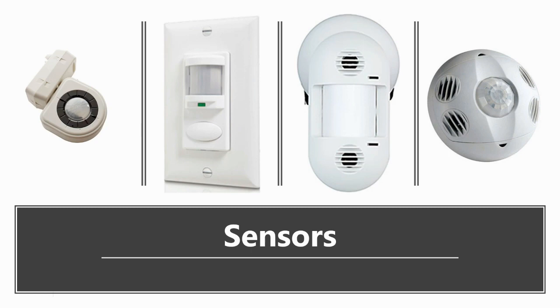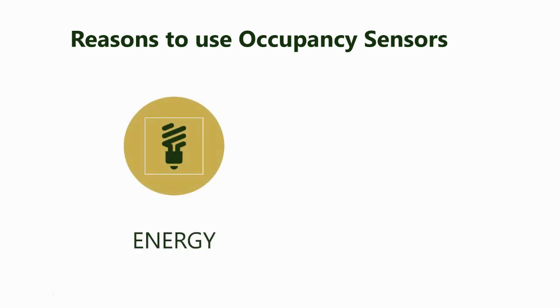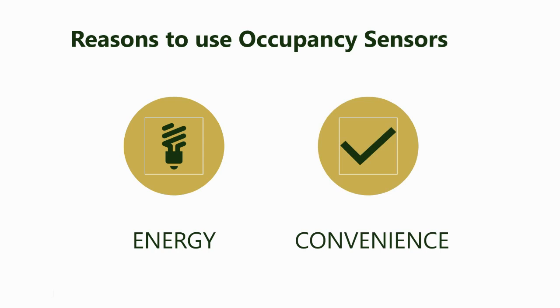By using sensors we can minimize electricity usage by turning on equipment only when it is needed. There are two good reasons to use occupancy sensors. The first is energy savings — using occupancy sensors can save approximately 25% of the electricity used just for lighting. The second reason is convenience. It's easy to forget to turn off the lights, and schedules can vary so time clocks may not always be accurate, which also makes sensors a great option for HVAC applications.